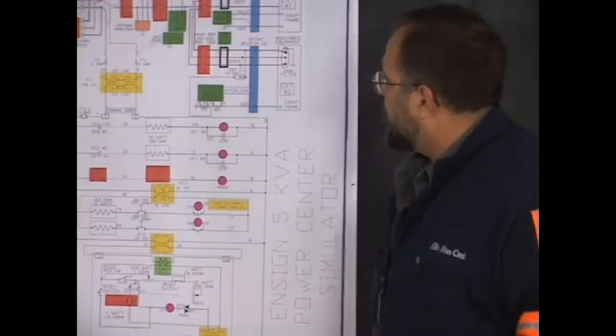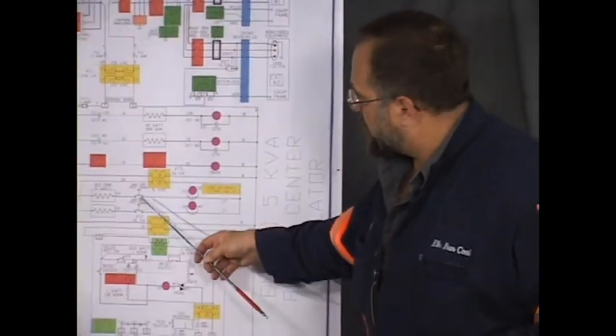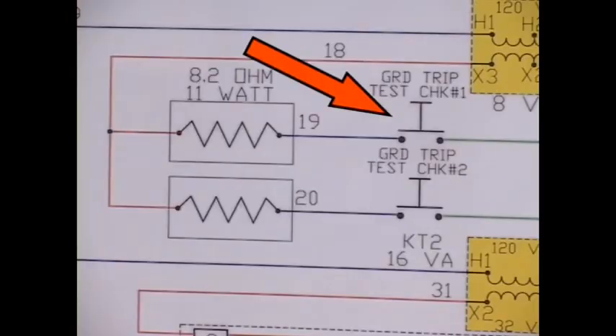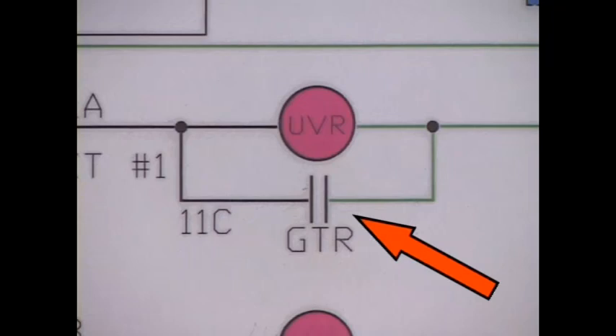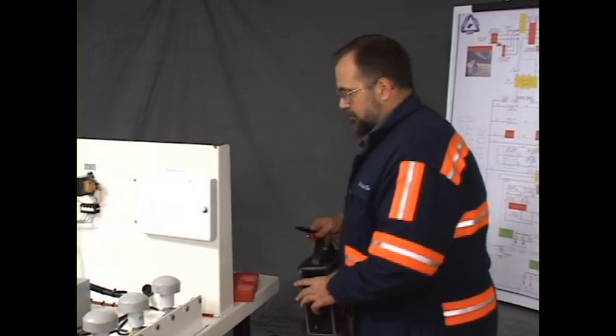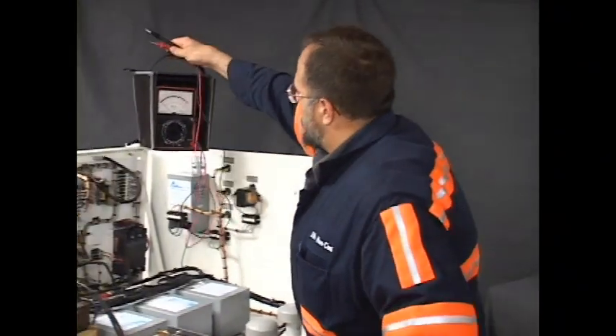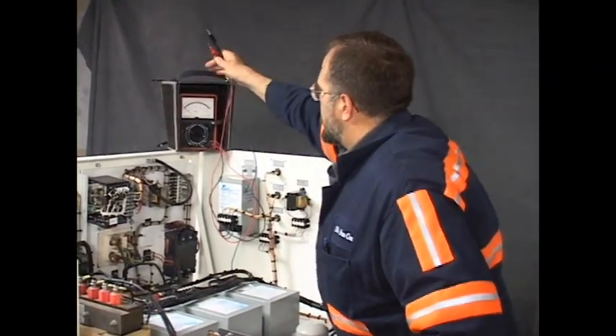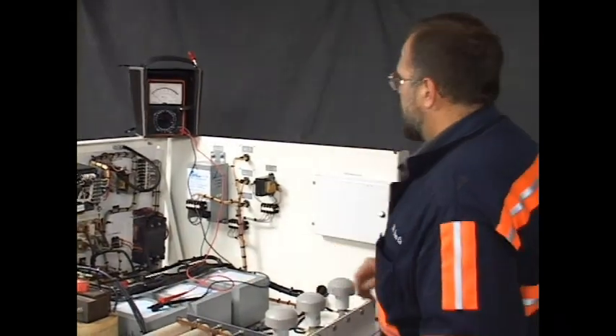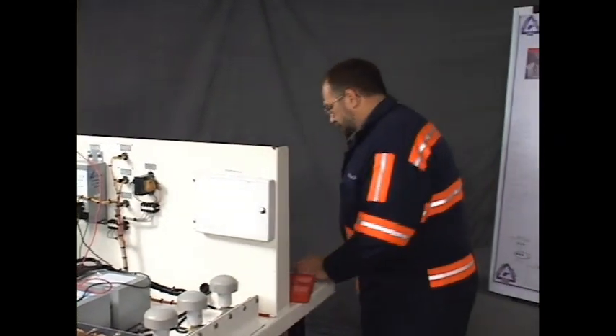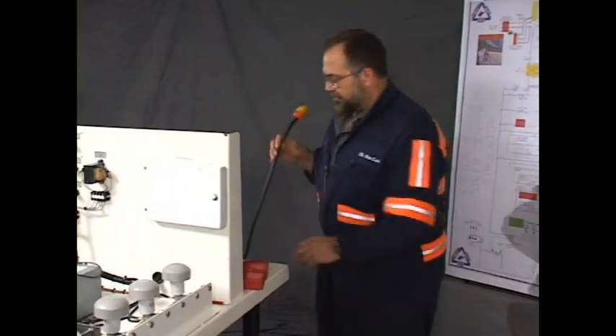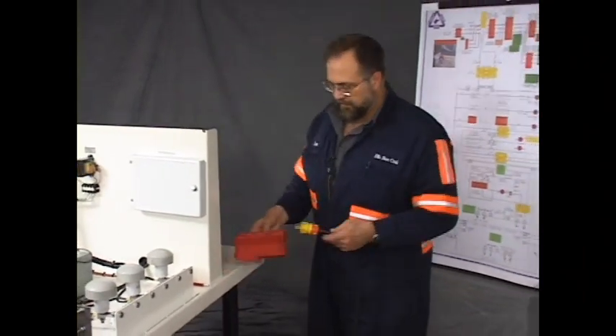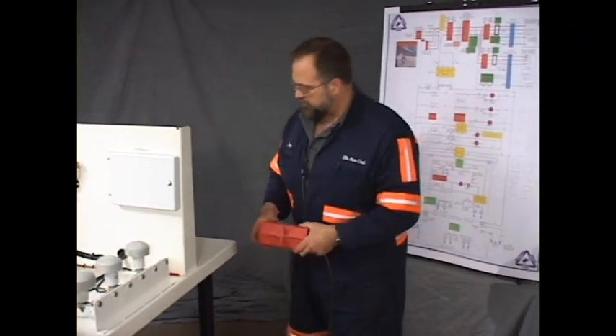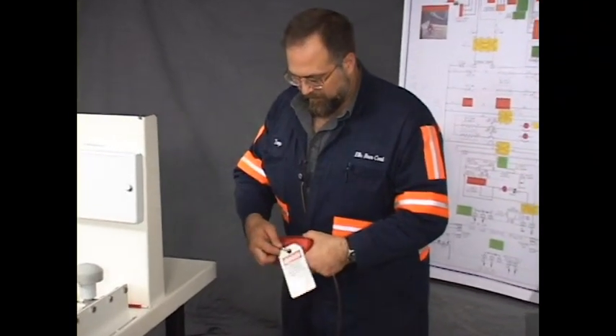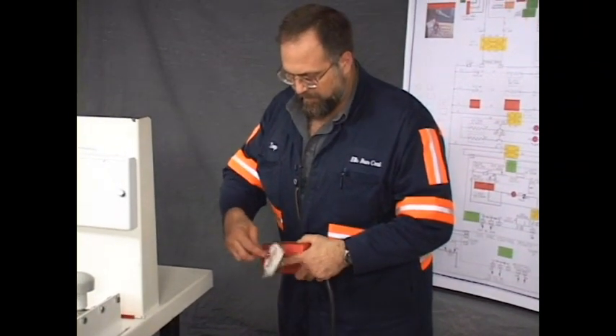So we have 2 points to check. We can check this switch, and we can check this GTR relay contacts. Let's go over to the skid here and do that. Okay, I'm going to take my meter, set it up in place here, preparing to troubleshoot this. And we're going to lock and tag. We already have a visible disconnect. This is a power cord for this skid. Place it in the lock box. Put an electrical lock on it and a danger do not operate tag.